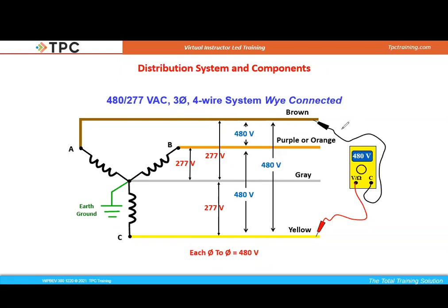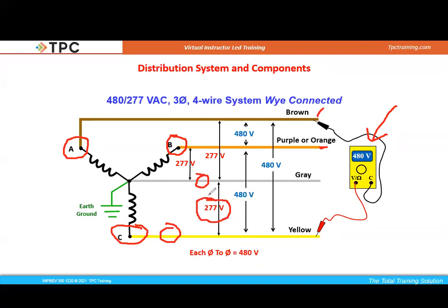Also, if we're going to test this, you can see if we go between any of these phases, if we go to the outside of this transformer configuration, anywhere between brown and orange or orange and yellow, we're going to get 480 volts. If we go from any energized conductor to our neutral, we would get 277 volts. And you want to be very careful. This is not a voltage that we should take lightly.